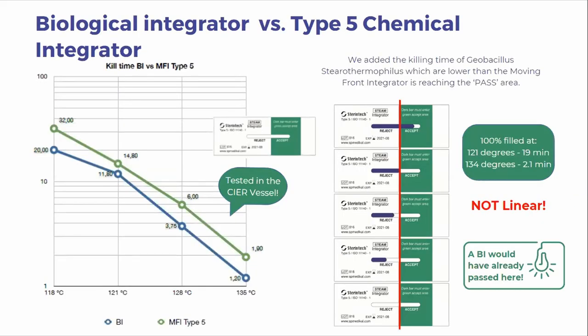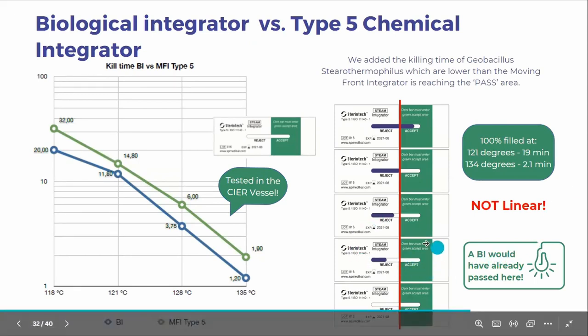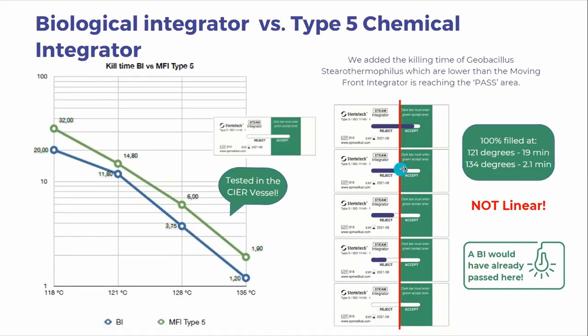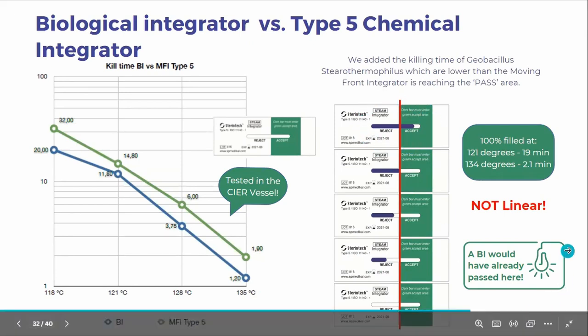So here we've added the killing time to the Geobacillus stearothermophilus, which are lower than the moving front integrators, reaching a pass area. So here the BI would have passed already. Only here the type 5 moving front integrators start to go into the accept window. Then at 2.1 minutes only, it will be fully colored.